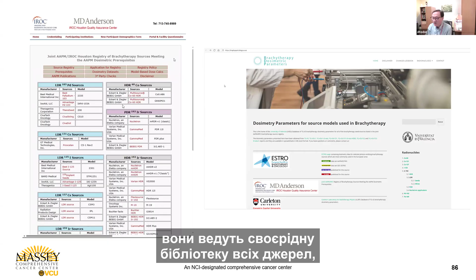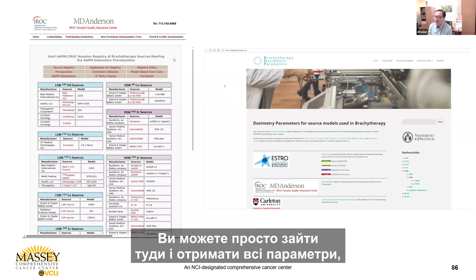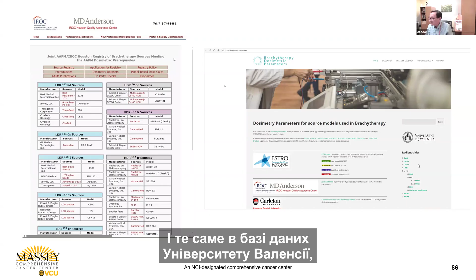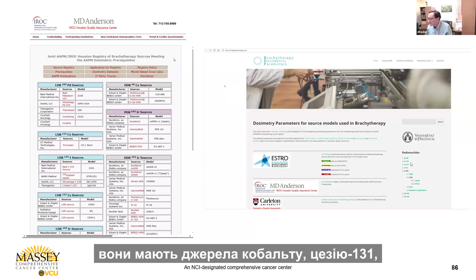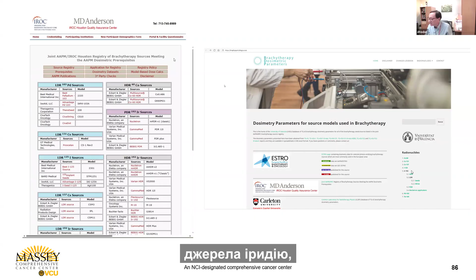And you can see here, MD Anderson has HDR cobalt sources, HDR iridium-192 sources. For each of those sources, these are publicly available. You can just go there and retrieve all the parameters, then you can check against your treatment planning system. The same thing in the University of Valencia database: they have cobalt sources, cesium-131, cesium-137, iridium sources, both LDR and HDR. So that's another very important thing to do.